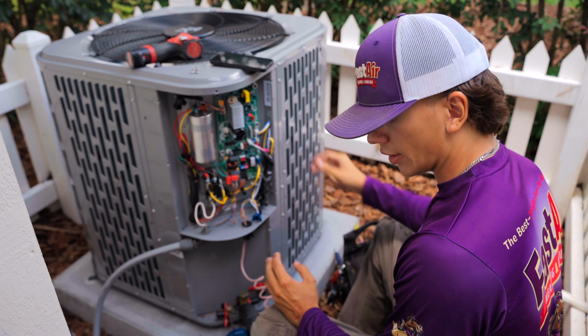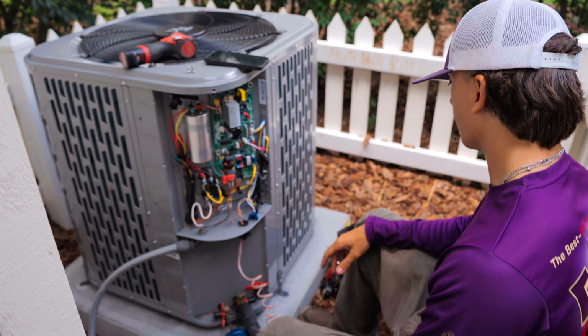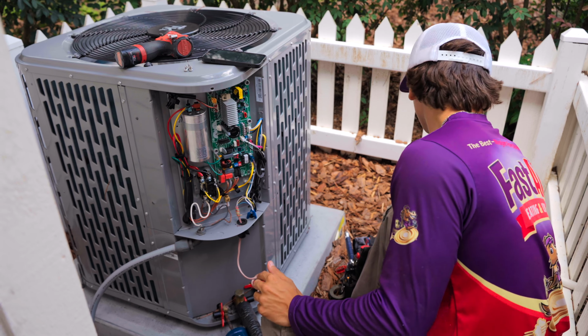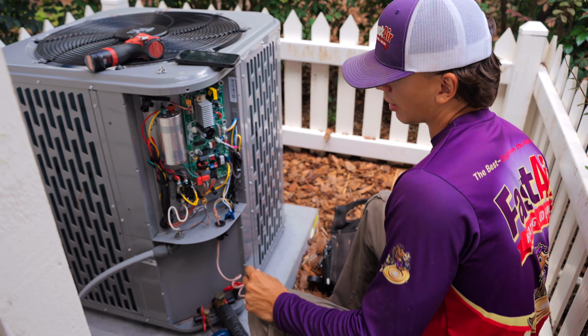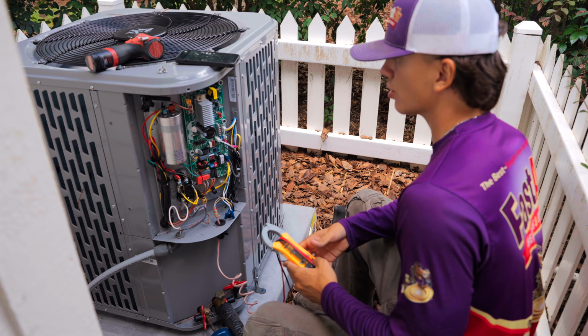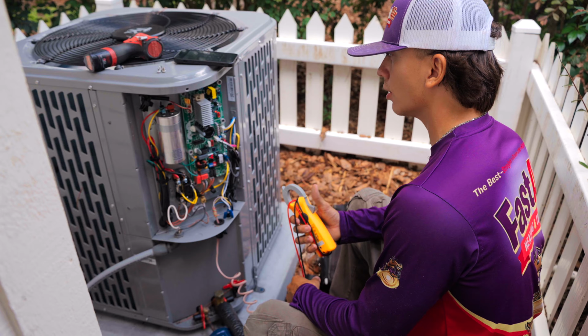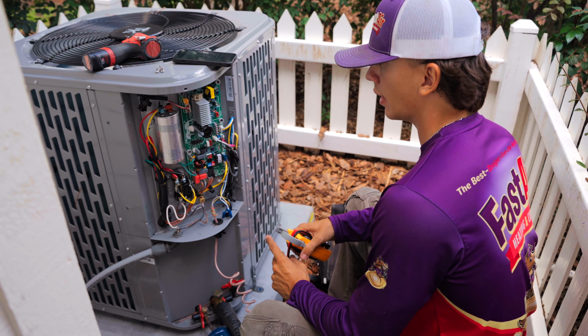Alright, so I just took the electrical panel off and read the data plate. I'm going to go ahead and start all of my electrical checks: check the compressor amperage, check the fan motor amperage, and then check the starting capacitor, and make sure the board is communicating with the whole system.